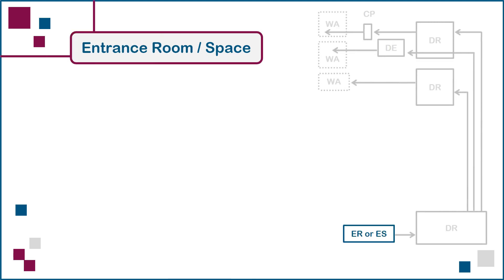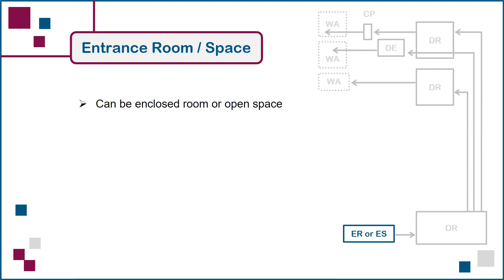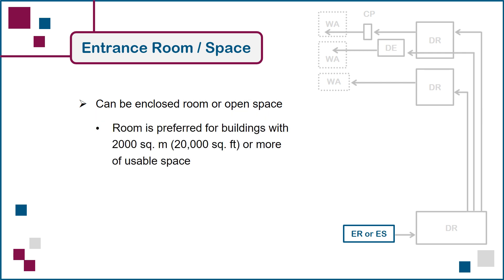We'll now look at each of these spaces individually and list the recommendations that should be considered by the cabling infrastructure designer, starting with the entrance room or space. Although it is allowable to use an open space instead of an enclosed room for the entrance of telecommunications cables into a building, a room is preferred for any building with 2,000 square meters or more of usable space.